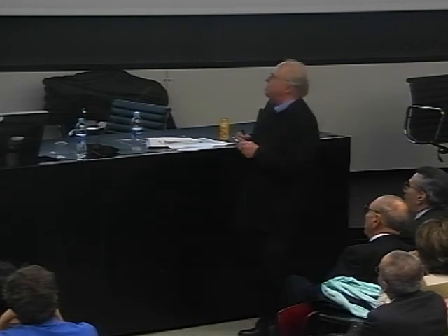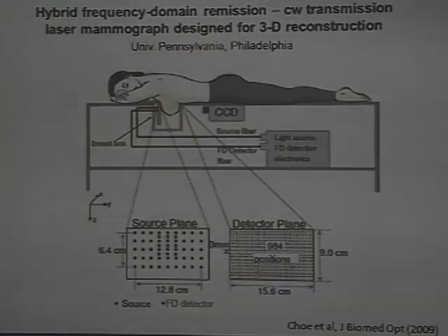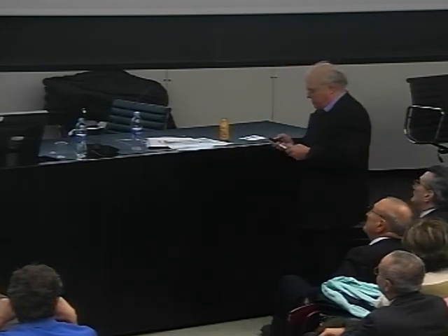And in order to reconstruct, you take 6 CW lasers, and you measure the diffuse transmittance, imaging the transmitted intensities by CCD camera, lens coupled to the output plane, and you do not do scanning like in the instrument here at the Politecnico, but you do fiber switching. We have a lot of source fibers. So what you do is you measure under many, many different viewing angles, and this allows you to reconstruct the optical properties, that is the concentration of the chromophores in 3D.